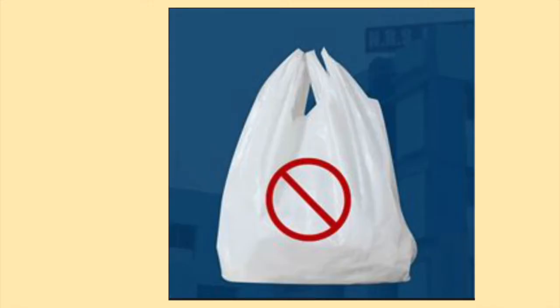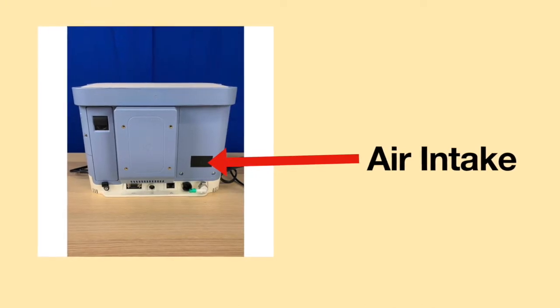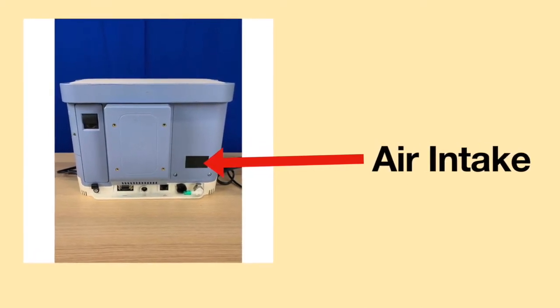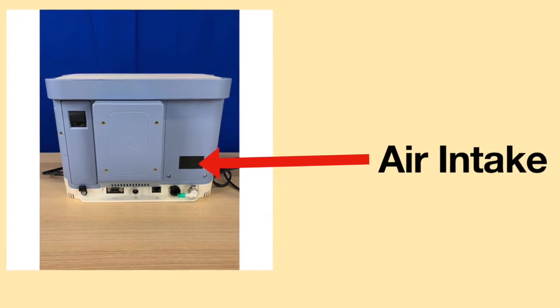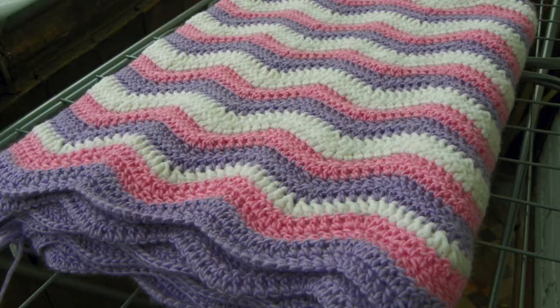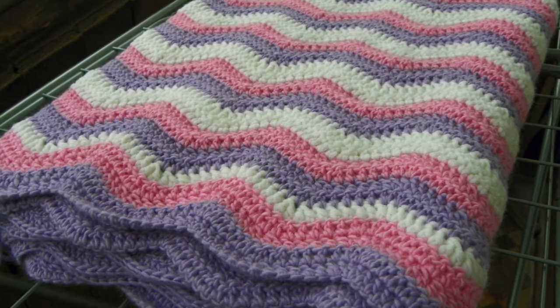If it is raining, please do not place a plastic bag over the ventilator. Remember, the air intake is on the back of the machine. A plastic bag blocks air from entering the ventilator. This will cause the machine to work overtime, produce excess heat, and shut down. To prevent the ventilator from getting wet, place a breathable blanket over the machine. This will keep the machine dry and will also allow the ventilator to continue operating properly.